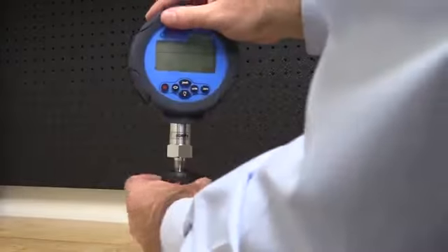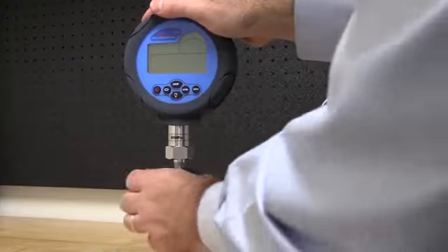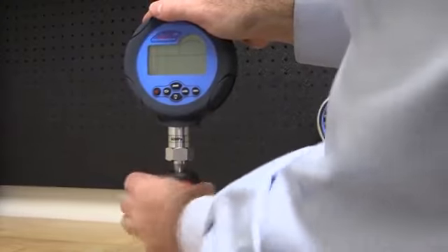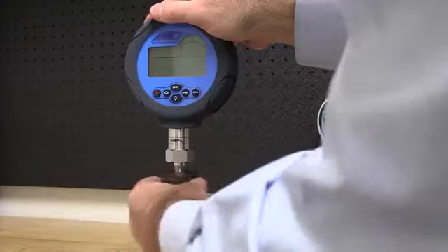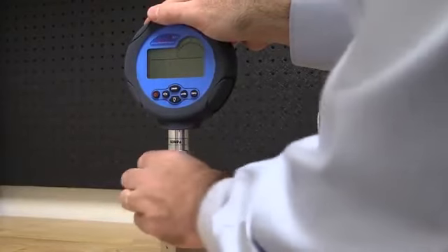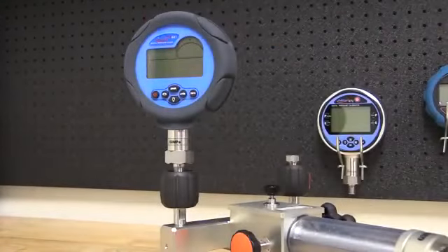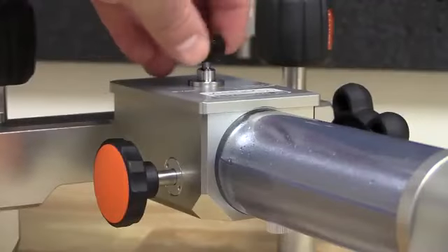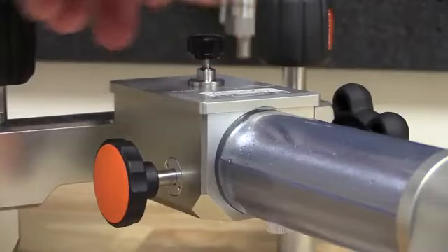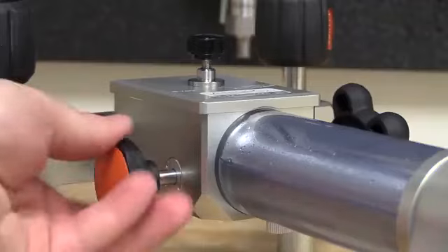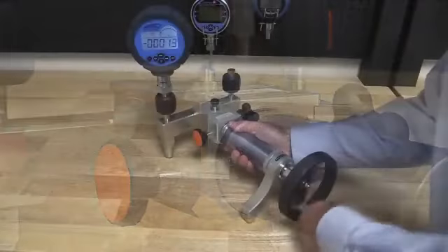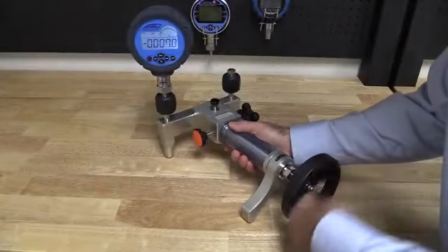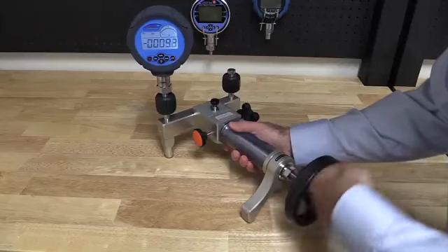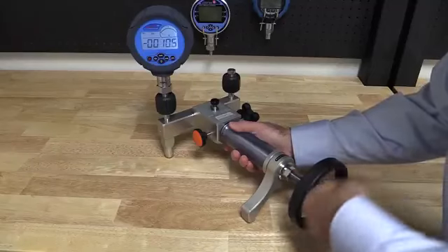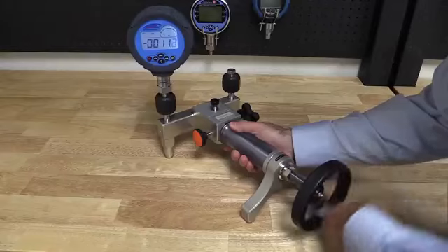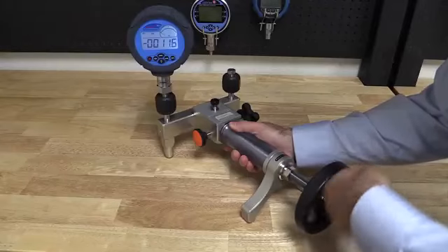The first step is to securely connect the reference gauge to the pump. The device under test, or DUT, could also be connected, but only if it is okay for the DUT to have a vacuum pulled on it. Next, ensure the reservoir release valve on the top of the pump is open. Then close the vent valve and screw out the main screw press. You'll notice a slight vacuum being pulled on your reference gauge. The strength of the vacuum can be a good indicator of the amount of gas in the system.